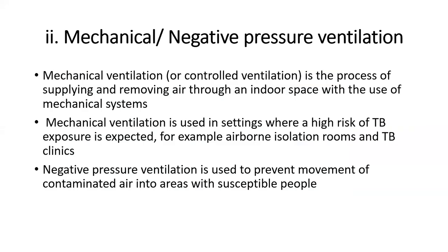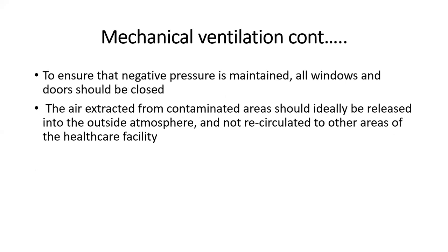Mechanical ventilation, or negative pressure ventilation, is a controlled ventilation. It is the process of supplying and removing air through an indoor space with the use of a mechanical system. It is used in settings where high risk of TB exposure is expected, for example airborne isolation rooms and clinics. Negative pressure ventilation is used to prevent movement of contaminated air into areas with susceptible individuals or patients. It's also to ensure the negative pressure is maintained.